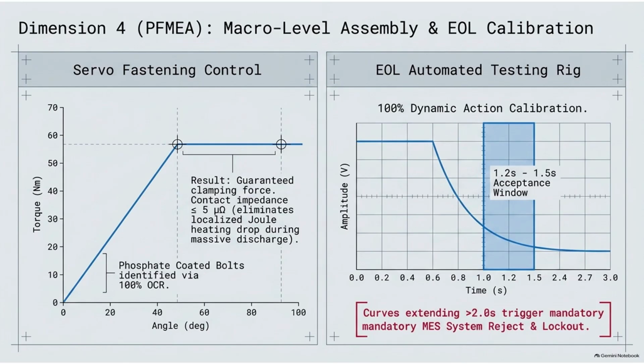If the bolt is even fractionally loose, the resistance at that joint increases. During a crash, when the system tries to forcefully dump massive violent amounts of electrical current through that joint to drain the battery, that slightly loose connection acts like a bottleneck. And a bottleneck creates friction. Electrical friction, which is joule heating. The formula is power equals current squared times resistance. Because the current is massive, even a tiny increase in resistance generates localized extreme heat.